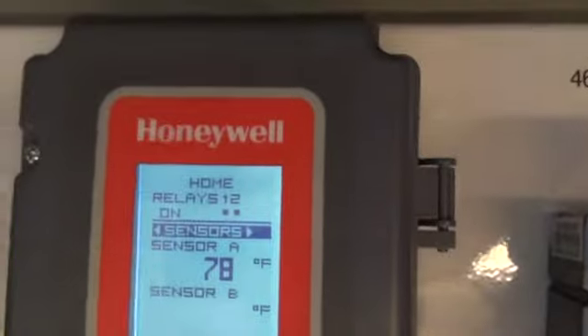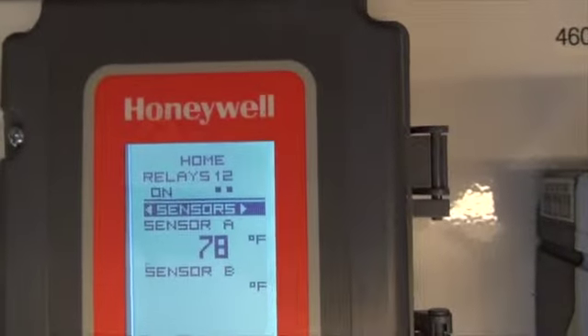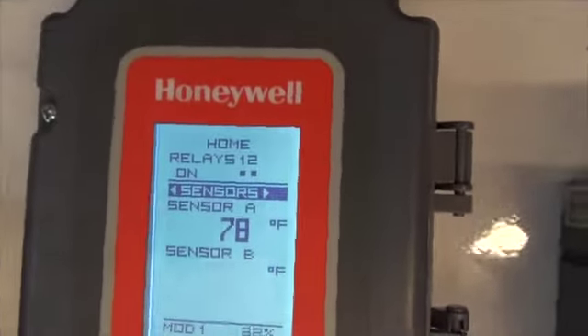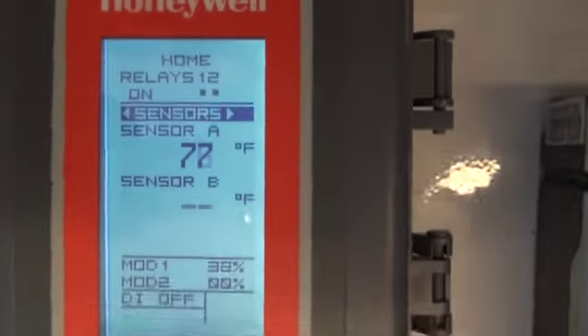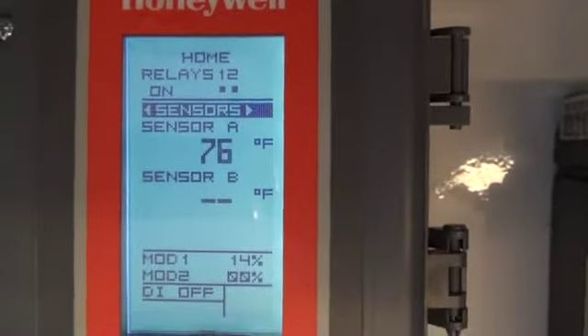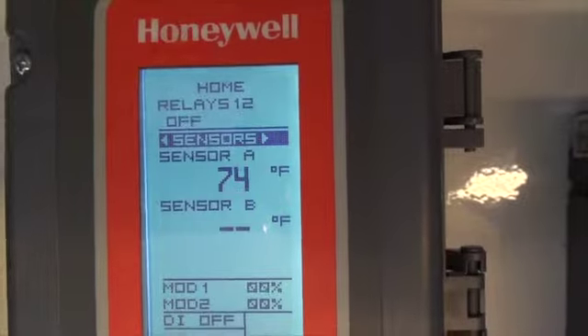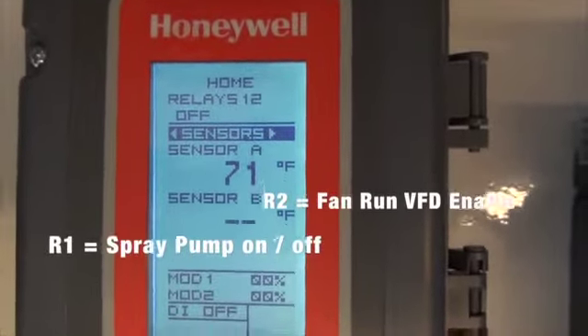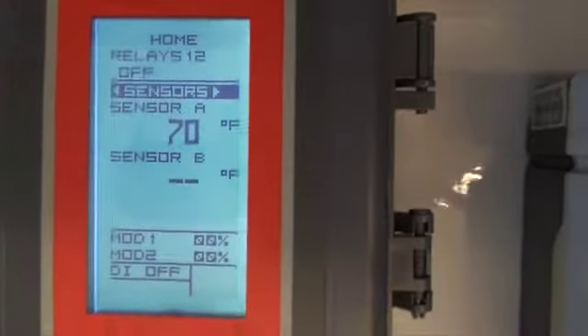Anyway, as you can see, as the thing heats up, relay 1 and 2 come on. So it's a really nice display to tell you what your water temperature is and what the status of your output relays are. Relay 1 is programmed for the spray pump. Relay 2 is programmed to enable the drive to run forward. So let's do some programming.